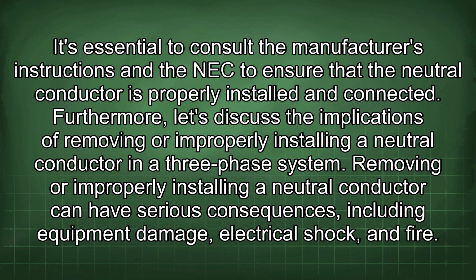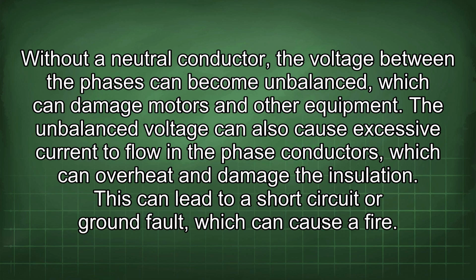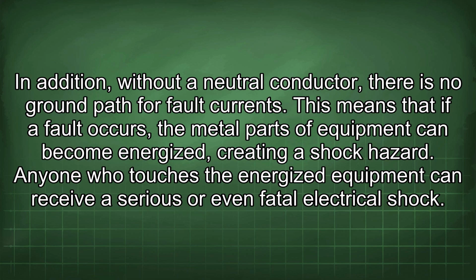Removing or improperly installing a neutral conductor can have serious consequences, including equipment damage, electrical shock, and fire. Without a neutral conductor, the voltage between the phases can become unbalanced, which can damage motors and other equipment. The unbalanced voltage can also cause excessive current to flow in the phase conductors, which can overheat and damage the insulation. This can lead to a short circuit or ground fault, which can cause a fire. In addition, without a neutral conductor, there is no ground path for fault currents.